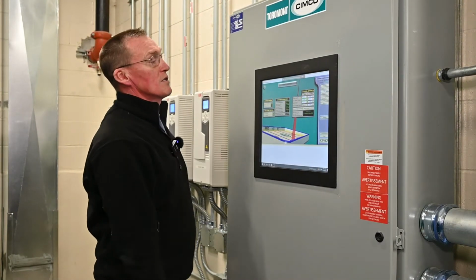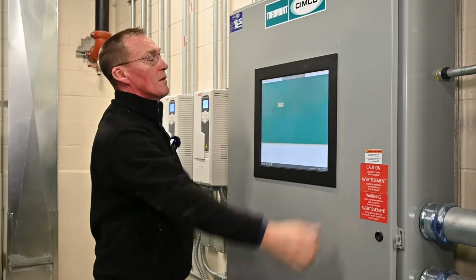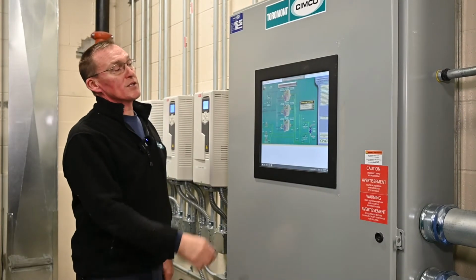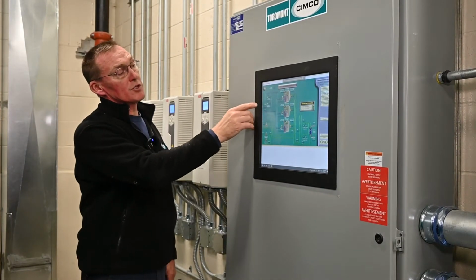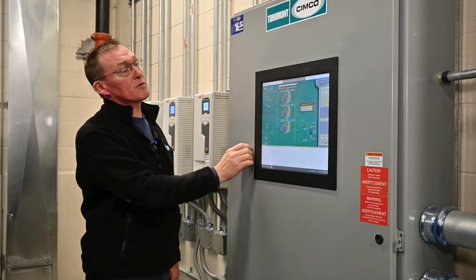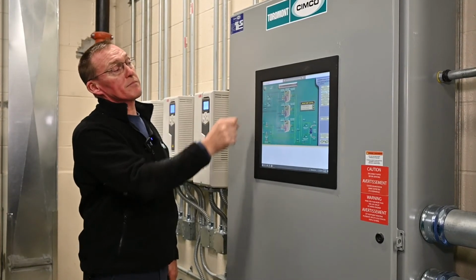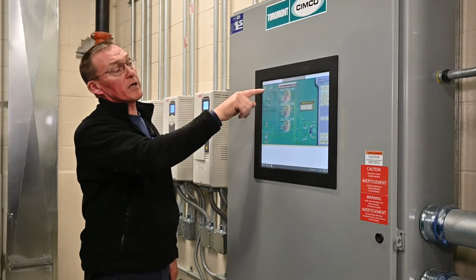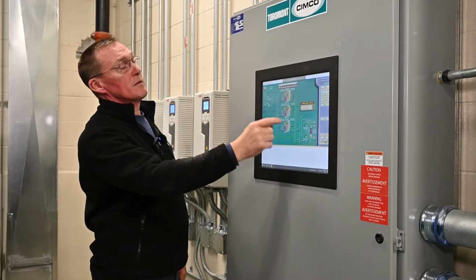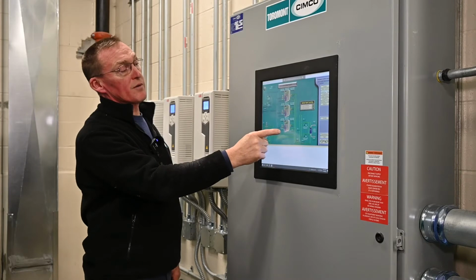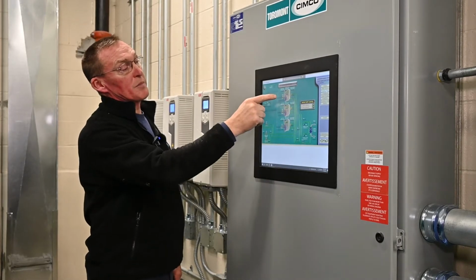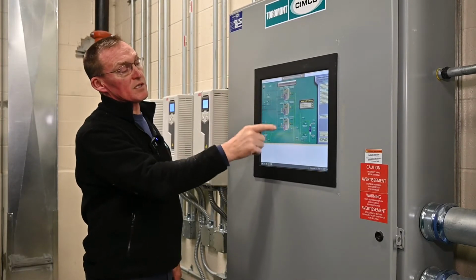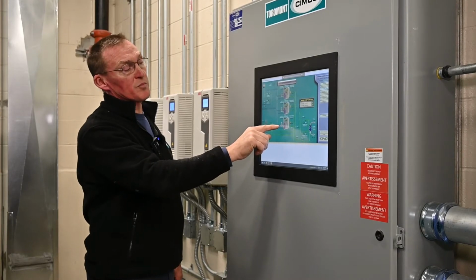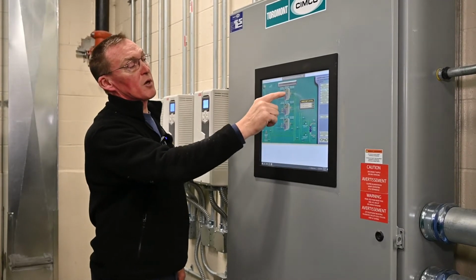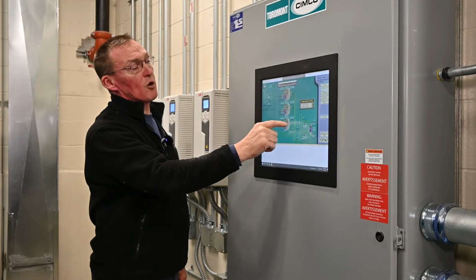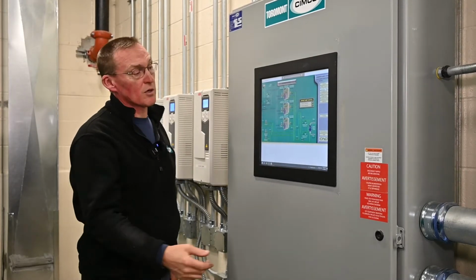Okay, system flow. Basically showing you P1, P2, showing you your glycol in and out temperatures, showing you your slab currently, and your target currently. Compressor 1, 2, and 3. Here are those GP1, GP2, GP3s. When you see these come online, you will actually see these spin in the bottom. And then you'll also see your Belimo valves open as soon as it decides to start one of the units.